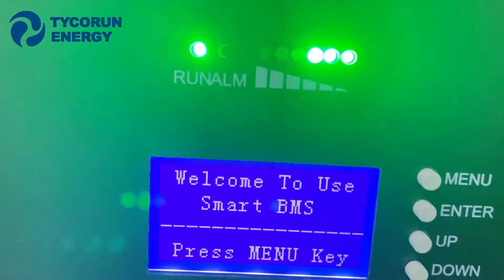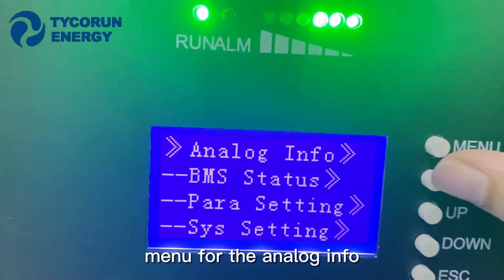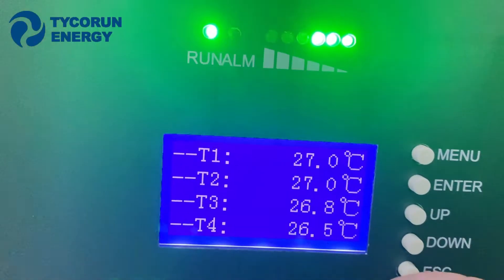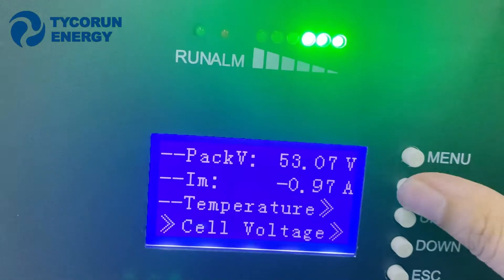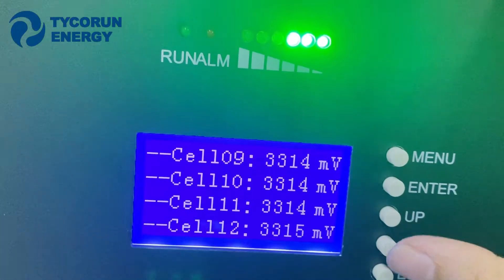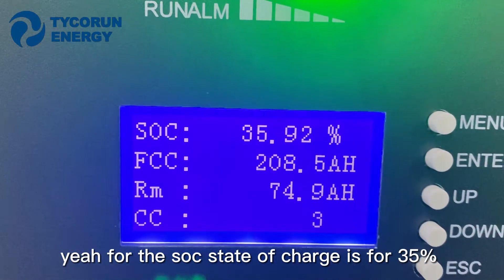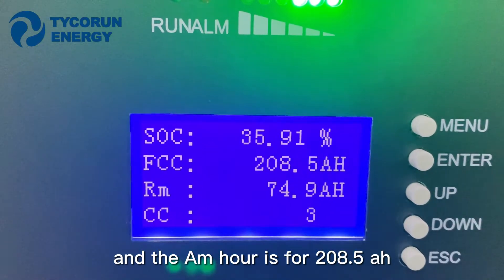Go to the menu view. In the menu screen, you can see the analog data in front — voltage, temperature, and cell voltage. You can see all of the cell voltages. For the SOC — state of charge — it is 35%, and the amp-hour reading is 208.5 Ah.